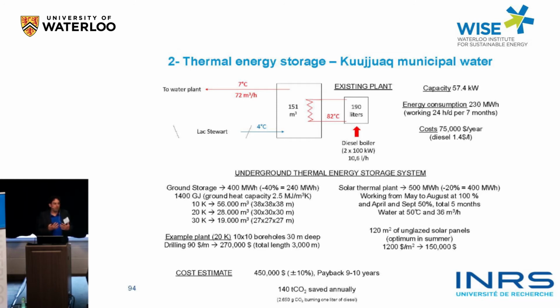And if we want to increase the temperature by about 20 kelvins, to have a heat exchanger plant, this would require about 10 by 10 boreholes, 30 meters deep, so 3,000 meters of borehole, for a total cost of almost $500,000. That could be with a payback time of 9 to 10 years, considering energy saving, to provide 100% renewable energy to heat the municipal water.